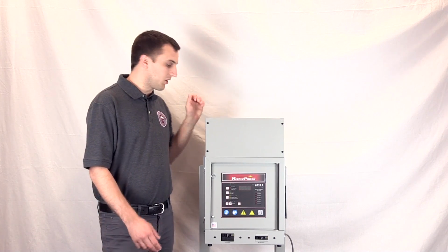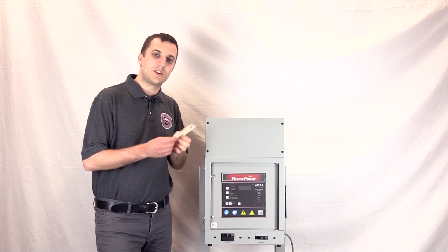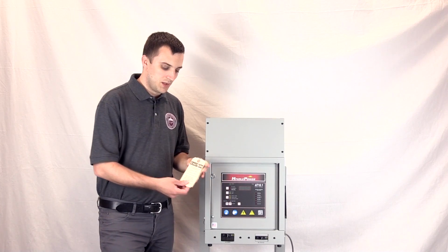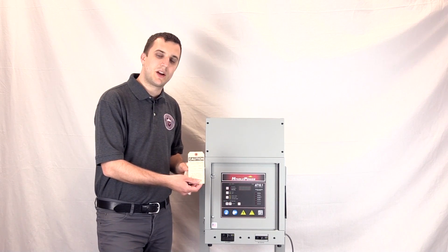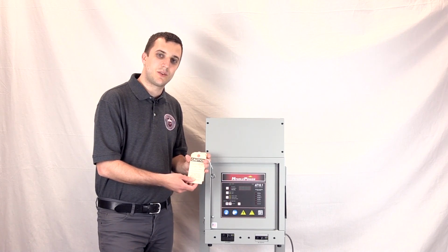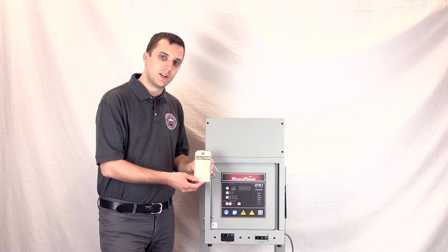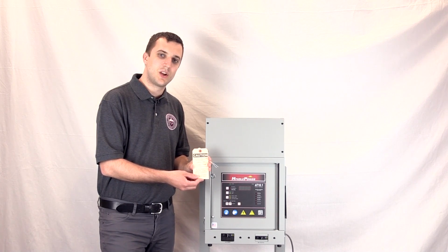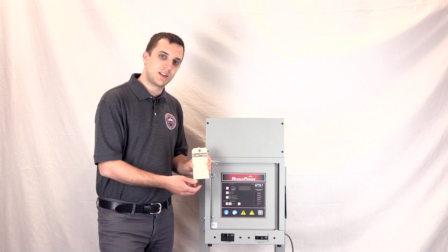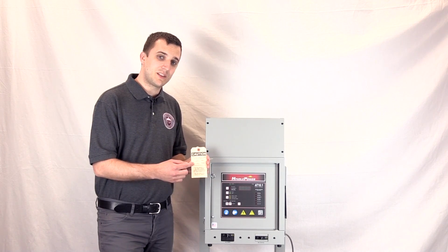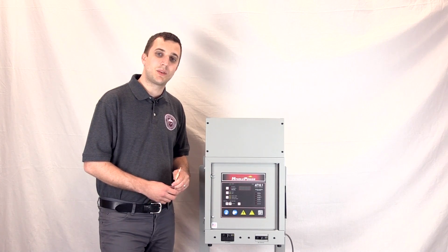First, every charger will have 2 manila tags that are attached to the front door of the charger. One of these tags is a caution label that will have the AC voltage that it was tested for at the factory written on it. So you want to verify your source voltage with that voltage on the manila tag. Also, you want to verify that the manila tag matches the data nameplate of the charger.